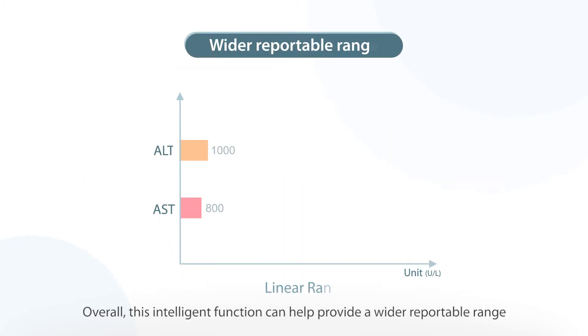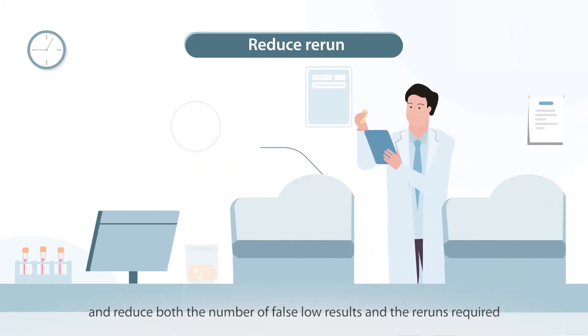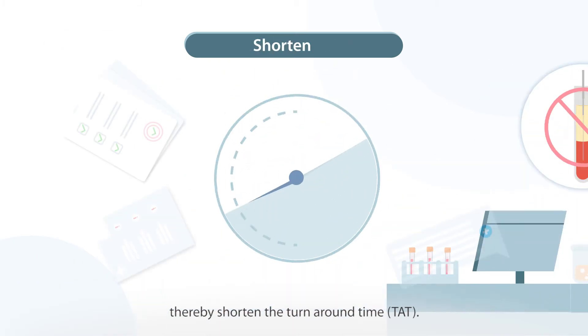Overall this intelligent function can help provide a wider reportable range and reduce both the number of false low results and the reruns required, thereby shortening the turnaround time.